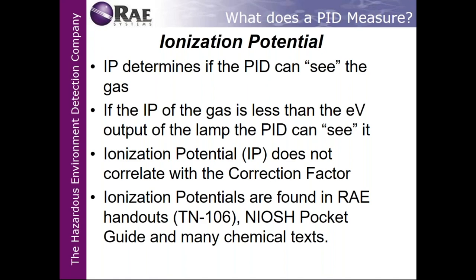that particular sample. The ionization potential does not correlate with the correction factor. It's totally different. Okay? When you have isobutylene, which has a correction factor of 1.0, on an isobutylene scale, all of the VOCs, not all of them, but a good majority that are in a NIOSH pocket guide or even in TechNote 106 will have a measurement or an eV so that you can quickly determine if this particular VOC has the ability to be ionized with the particular lamp that you have. In this case, with acetone, we have a 10.6 lamp. Acetone is 9.71. So it's lower than 10.6, it will ionize.